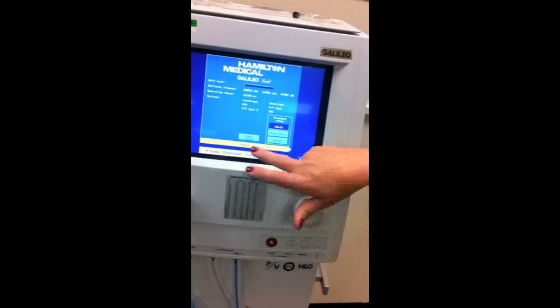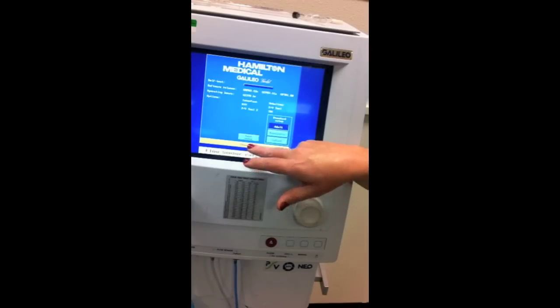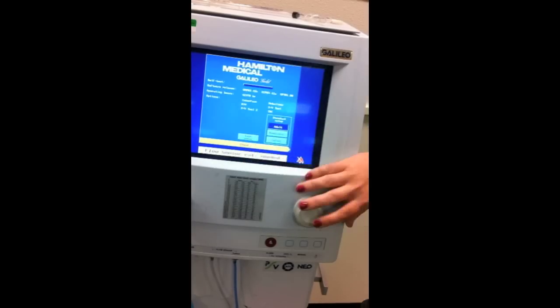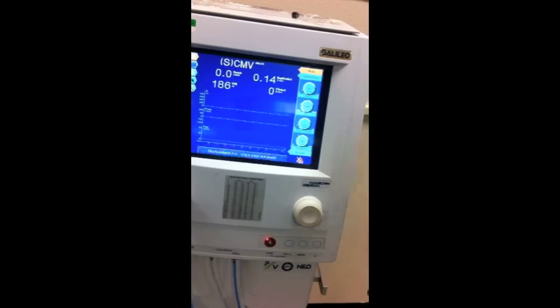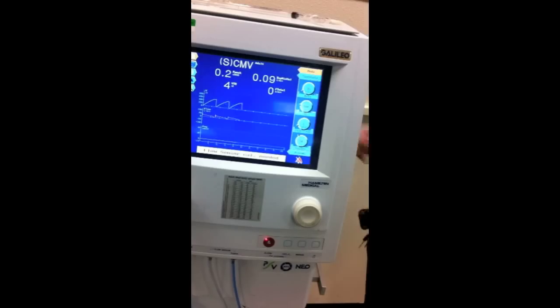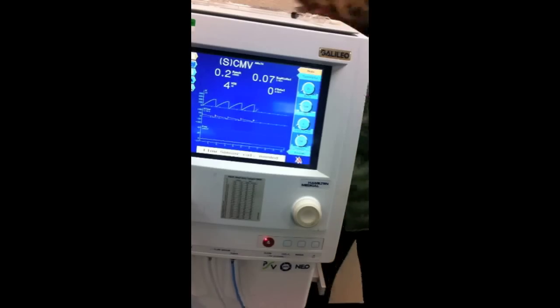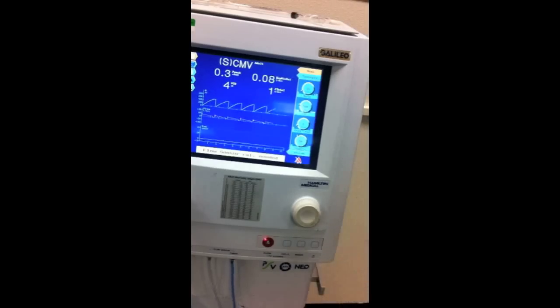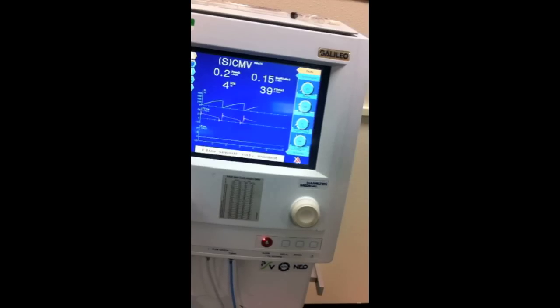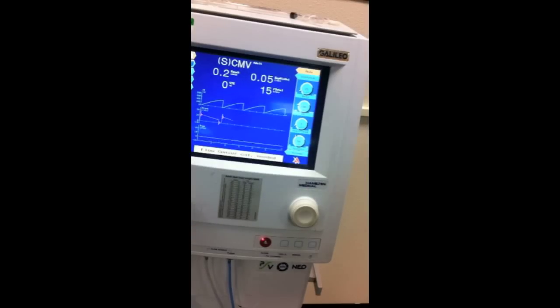So you got to press the button wherever the orange is, where the scroller is right now, and so we're going to push that to do start, and we'll come on over to this screen here. It's telling us that a flow sensor calibration is needed. The calibration for this ventilator is not as fancy schmancy as all the other ones. Some of it we do the old-fashioned way. We have this little card that says pre-operational check on it.